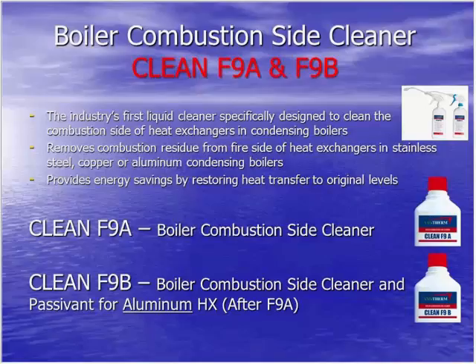So if you're cleaning a stainless steel or copper heat exchanger, you use the F9A cleaner only. If you're cleaning an aluminum heat exchanger, it's a two-step process. Use the clean F9A, then the clean F9B. The reason for that is aluminum doesn't like caustic solution, so you spray on an acid to counteract and neutralize that. That's also going to passivate the aluminum and put that natural aluminum oxide barrier back on the aluminum that's naturally going to protect it from corrosion.